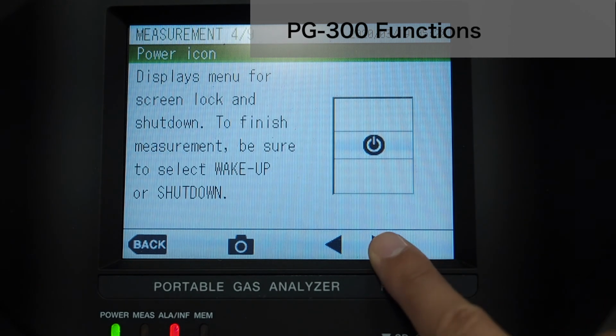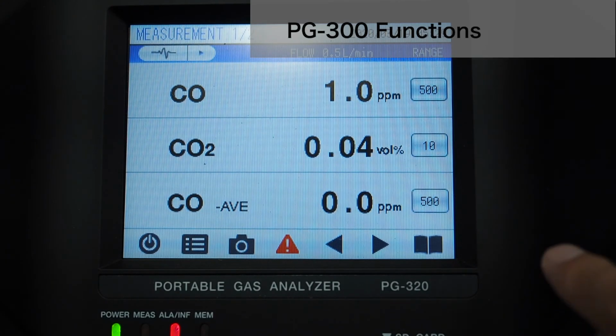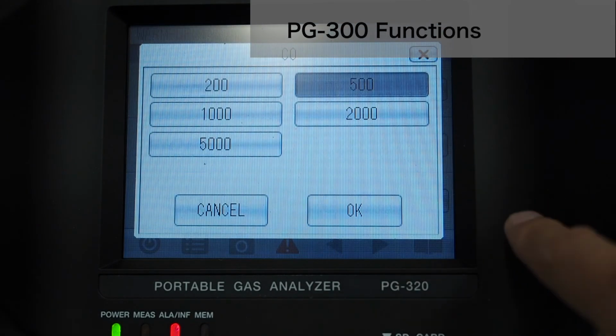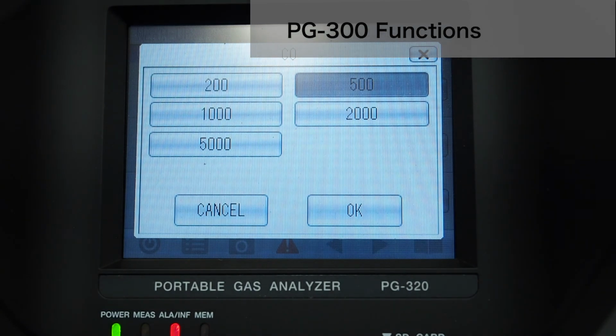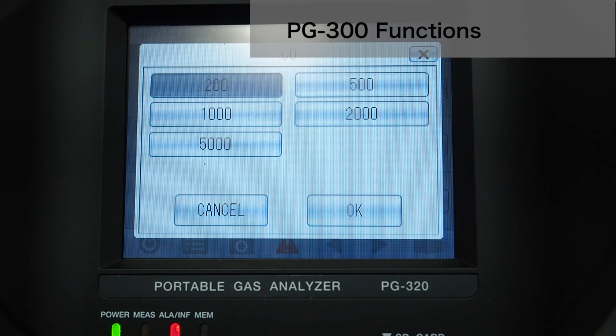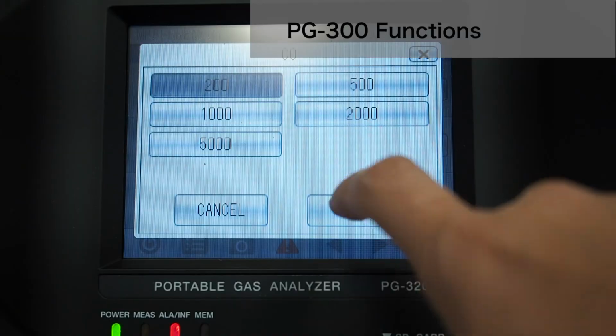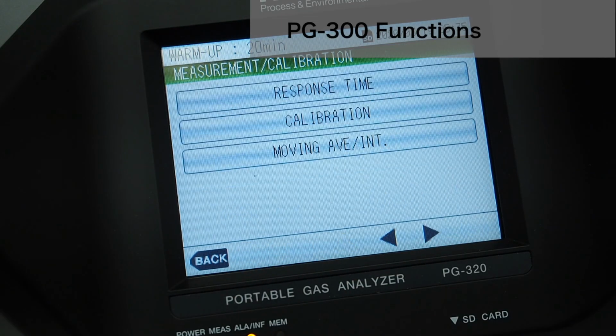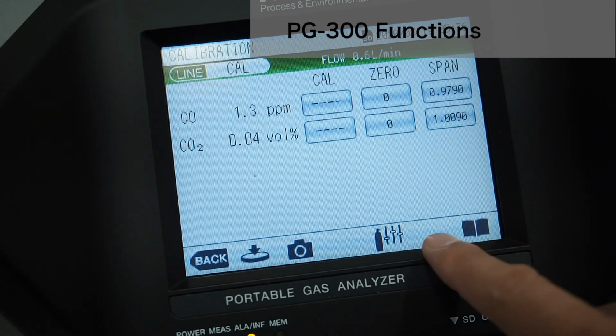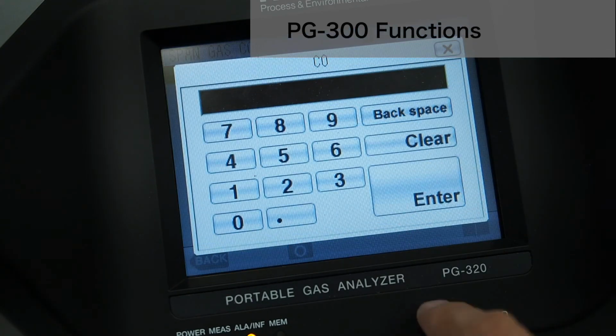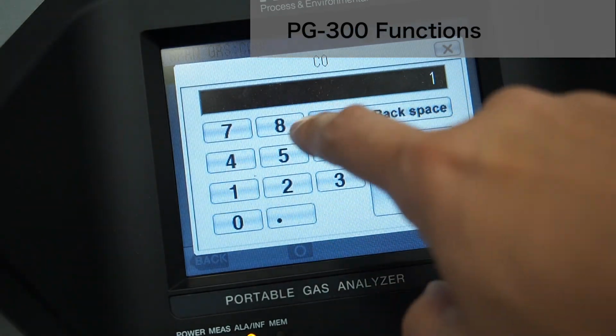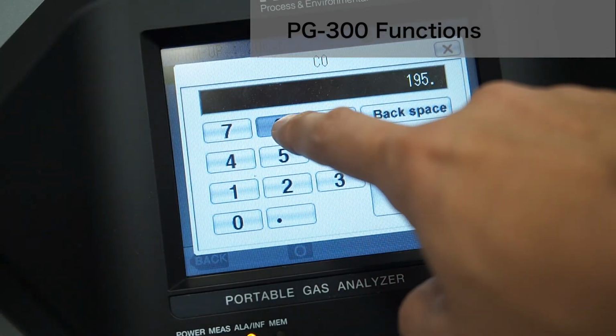So you always go with the manual. You never get lost. Changing range is very easy. Please see the range on the right. Once you touch it, you can select from the ranges provided. Calibration: go through this CAL button, which takes you to the CAL mode, enter your cal gas concentration, and execute calibration. That's it. Make sure you connect the cal gas with the line.